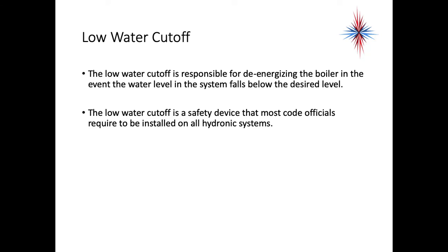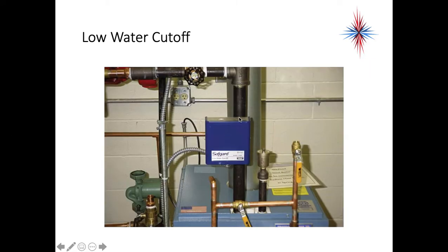Every boiler must have a low-water cutoff — it's part of building code. The low-water cutoff shuts down or de-energizes the boiler if the water level falls below the desired level. It's a safety device required on all hydronic systems. The worst thing would be to energize a boiler without water in it — that's why boilers used to explode before low-water cutoffs existed. The operation of this device must be checked every time you service a boiler.